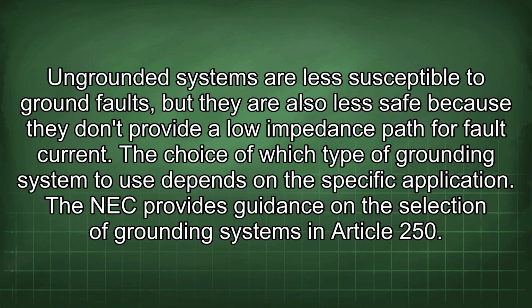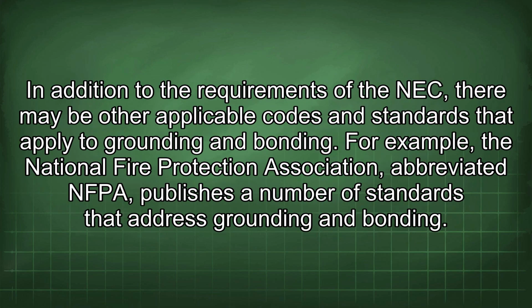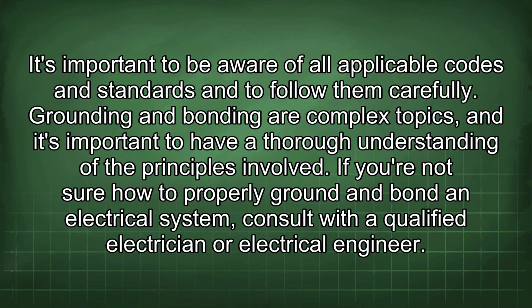The choice of which type of grounding system to use depends on the specific application. The NEC provides guidance on the selection of grounding systems in Article 250. In addition to the requirements of the NEC, there may be other applicable codes and standards that apply to grounding and bonding. For example, the National Fire Protection Association, abbreviated NFPA, publishes a number of standards that address grounding and bonding. It's important to be aware of all applicable codes and standards and to follow them carefully.